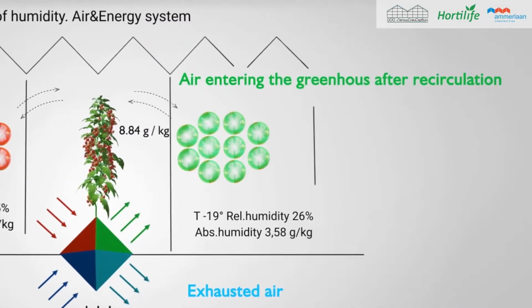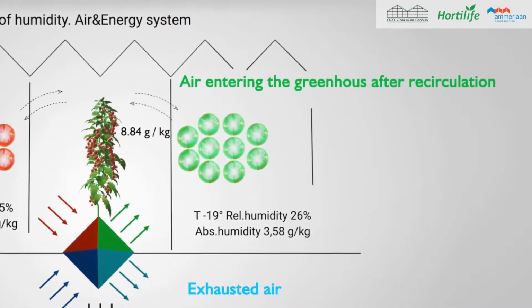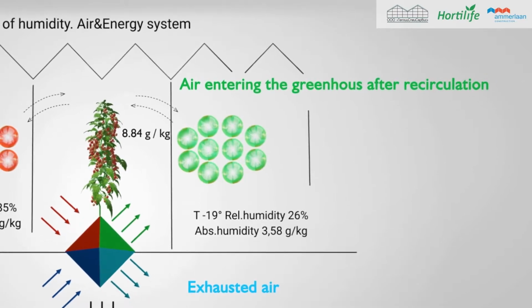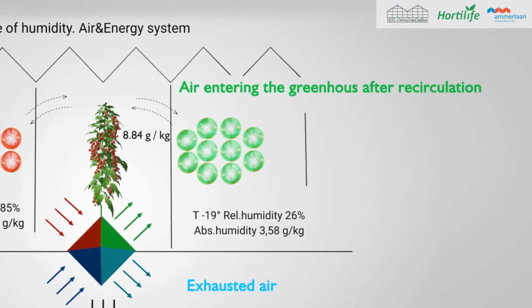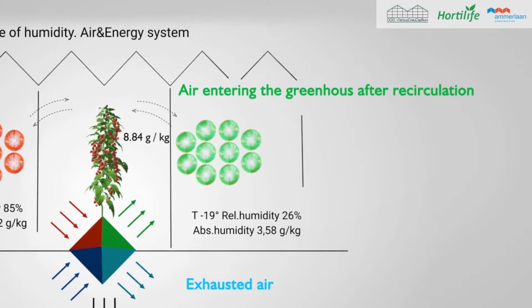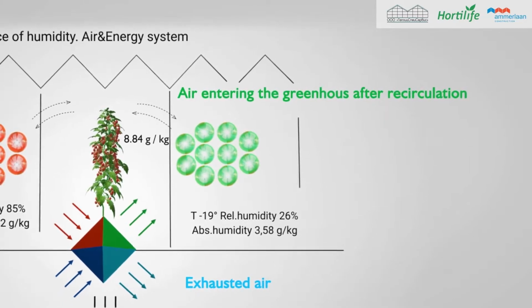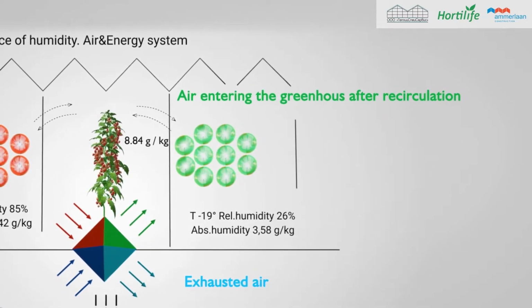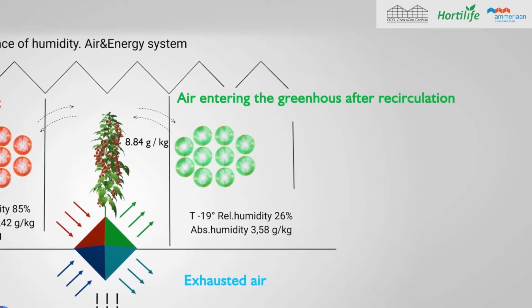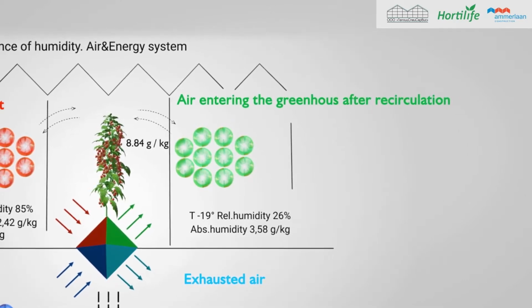The incoming air from the outside, passing through the plates of the heat exchanger, is heated by the energy of warm air from the greenhouse without mixing with it. By doing so, the absolute humidity does not change, and the relative humidity decreases from 85% to 26%.